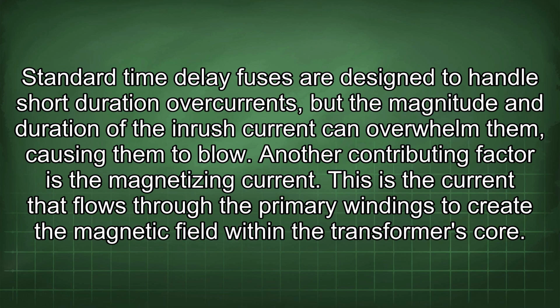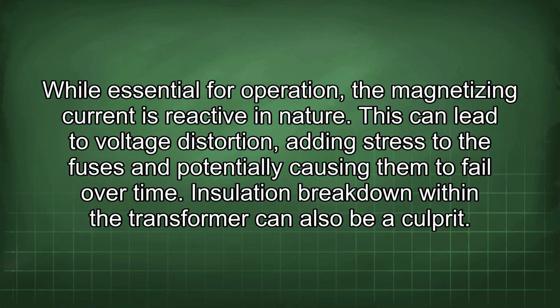Another contributing factor is the magnetizing current. This is the current that flows through the primary windings to create the magnetic field within the transformer's core. While essential for operation, the magnetizing current is reactive in nature. This can lead to voltage distortion, adding stress to the fuses and potentially causing them to fail over time.